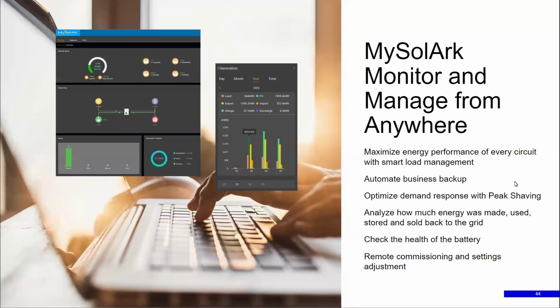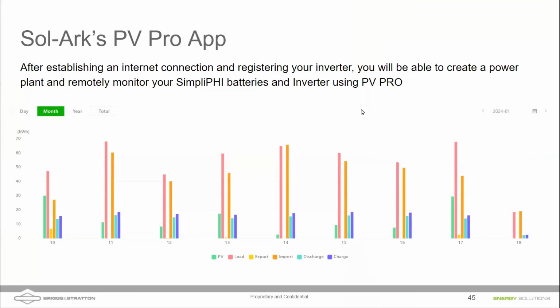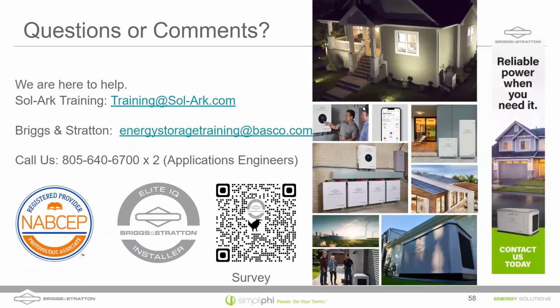Granted, you'd have to stay within the limitations of the system. Given how rare it is that you would have a Sol-Ark failure and the Sol-Ark failure take out the grid connection, and this is true of any type of system architecture, period, that grid connection point could fail, the only way around that scenario is a second grid connection point. And so at that point, it's how much money do you want to put into it? Do we have installers putting in 200 amp manual throw switches? Yes. Do most of our installers do that? No. So I'd say a middle ground between a $2,500 200 amp manual throw switch and nothing at all is to double lug, maybe even off the external disconnect, and land a generator interlock on top of the main service panel.